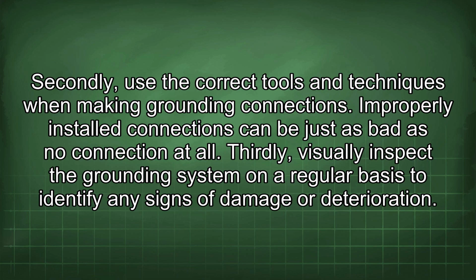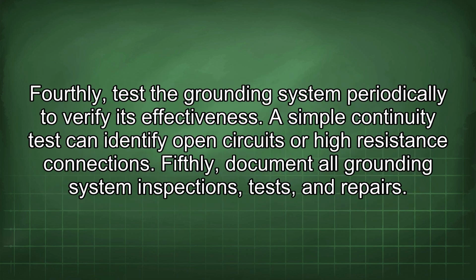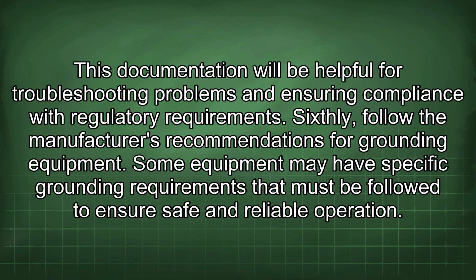Secondly, use the correct tools and techniques when making grounding connections. Improperly installed connections can be just as bad as no connection at all. Thirdly, visually inspect the grounding system on a regular basis to identify any signs of damage or deterioration. Fourthly, test the grounding system periodically to verify its effectiveness. A simple continuity test can identify open circuits or high resistance connections. Fifthly, document all grounding system inspections, tests, and repairs. This documentation will be helpful for troubleshooting problems and ensuring compliance with regulatory requirements.